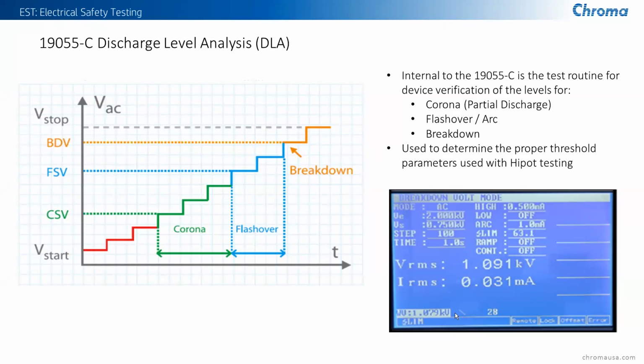are able to, with the very high sample rate, detect at very low levels these different types of changes in the actual current changes for corona and for flashover. And we've got another slide that covers this in more detail, but I've also shown a screenshot of it. Over here, the screenshot on the front of the unit will give you a particular measurement in current for the arc detection at a different current level. It also gives you a proportional number for the peak measurement of the corona, which is a 0 to 99 reference proportional value that would indicate that you're starting to see some level of corona occurring.